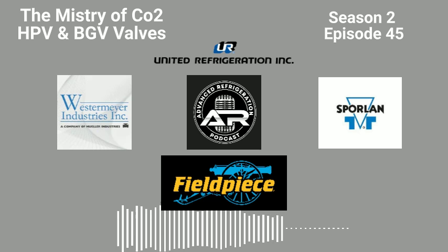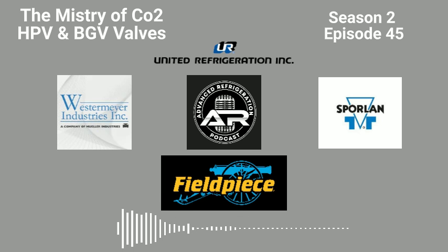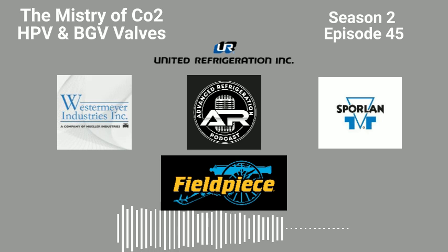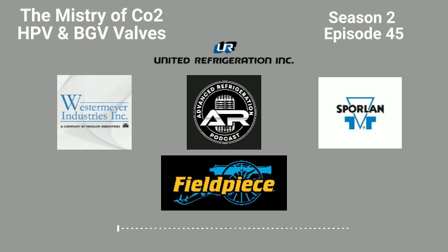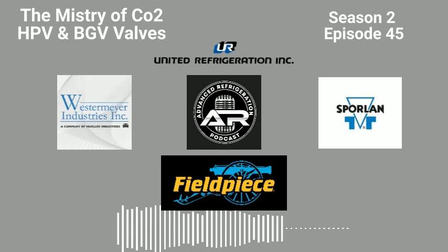This controller, without it, the rack's dead in the water. If you lose a high pressure valve driver, say if you have an external driver, yeah, you can make it work with the E2 and some fancy programming and logic. I've done it, but if you lose that valve driver that's putting out the algorithm, you're done. You're not running that rack unless it's super cold outside. I'm curious how you did it. That'll be another episode. You do that later.